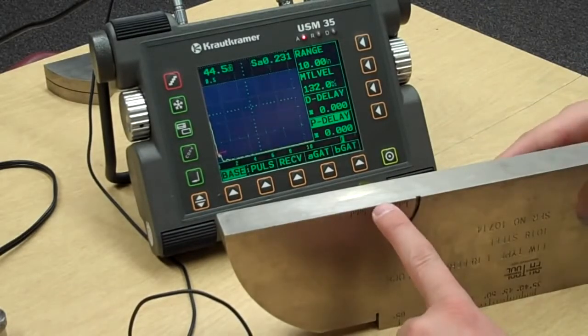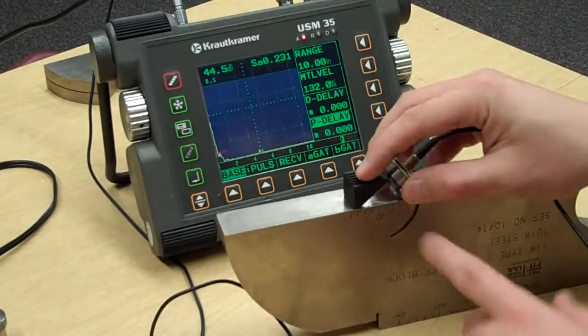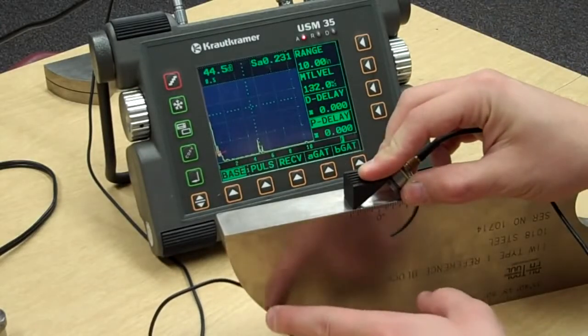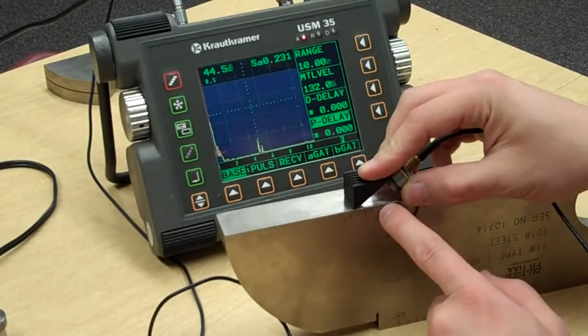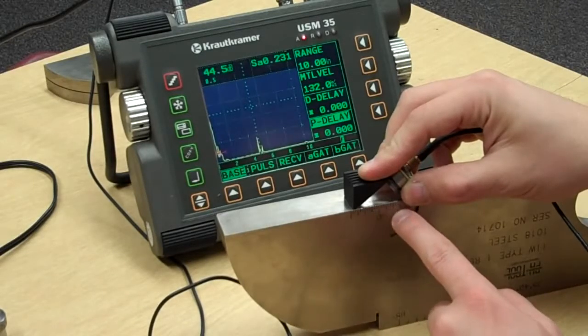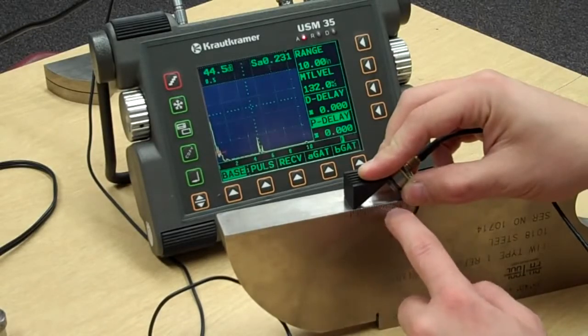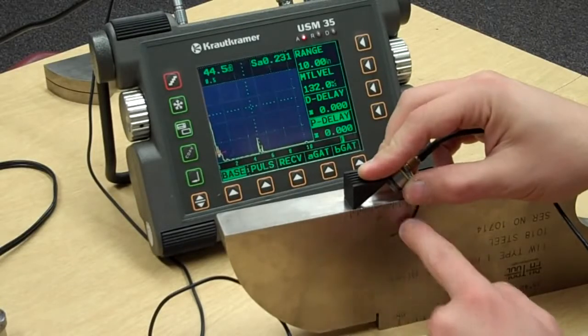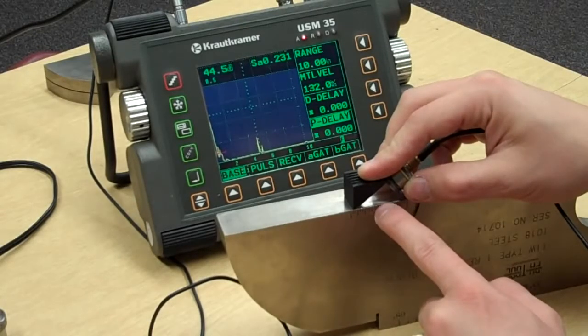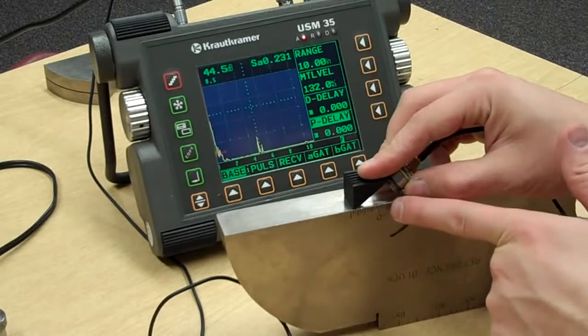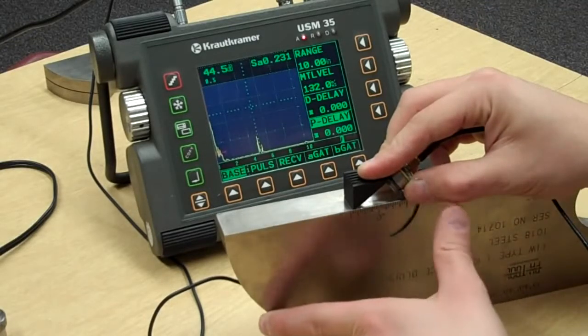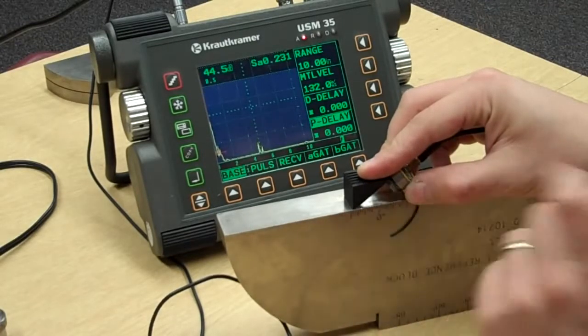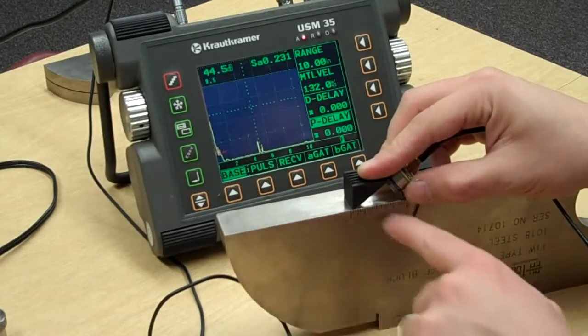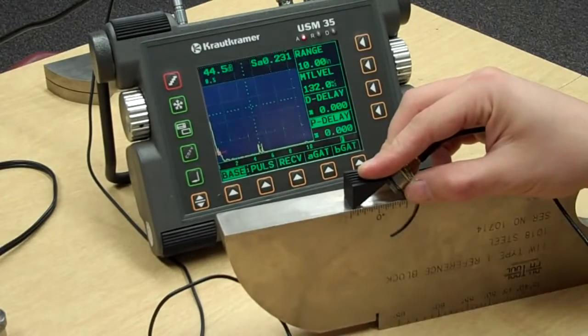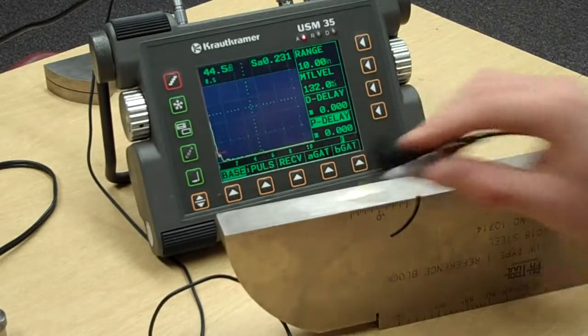So what's going to happen is we're going to put our transducer on here like this. Sound's going to come down, going to bounce off at 4 inches. Okay? Some of it's going to be reflected back, some of it's going to continue on. So then it's going to add another inch, but the sound's going to be coming up this way, so transducer can't receive it if it's pointed this way. So it bounces and goes back down, comes back, and then we pick it up again at 9. So 4, 9. First signal at 4, second signal at 9. Looks like we still got a little coupling on the block because we got a couple signals already.